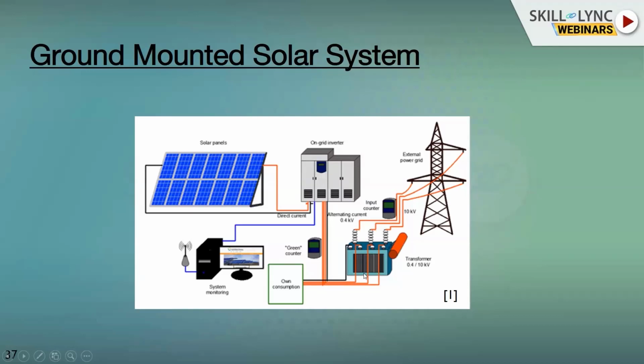The inverter converts DC into AC and connects it to the transformer. The transformer converts the voltage because solar panels produce only low voltage, ranging from 400 to 800 volts, which cannot be used for the grid system that has nominal voltages like 11 kV, 33 kV, or 66 kV. For that, we need to step up the voltage level using a transformer, which steps up the voltage to connect to the grid.